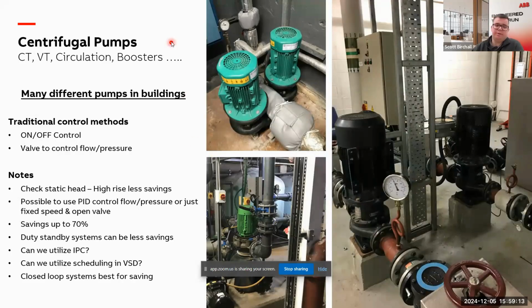Centrifugal pumps as well. Traditionally, many different pumps in buildings and across different applications are controlled on-off or by valve, so you're just pumping against a semi-closed valve, burning energy really, not saving at all. Again, savings up to 70%. These are the easiest ones to understand and to save with, in terms of reducing the speed to get the most return.